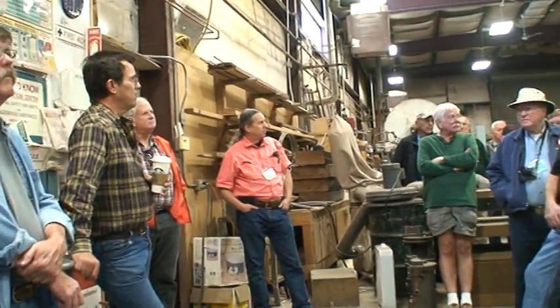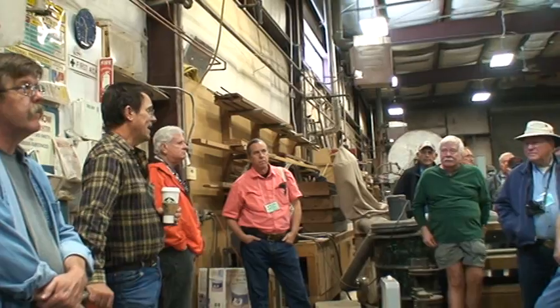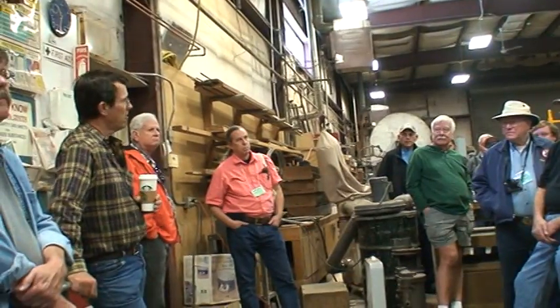Chris, did you do the ultrasound? Which one? The one on the pressure vessel and the dry pipe? I did personally, and that's what I put in my engineering report that's being reviewed. It's like 35 pages of notes typed out with the calculations and drawings and sundry. That's what's being reviewed by the professional engineer. He's not obligated to verify dimensions. He's just looking at my numbers and making sure the calculations are valid, and that the numbers supplied actually work within those calculations. It is the inspector's responsibility to come up and UT and otherwise measure to verify that the numbers I supplied to the PE are accurate.